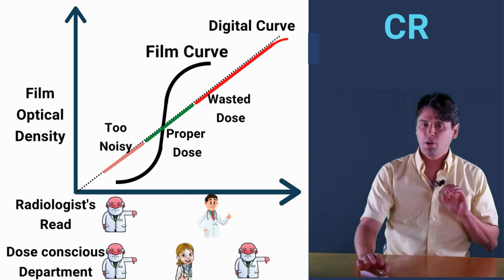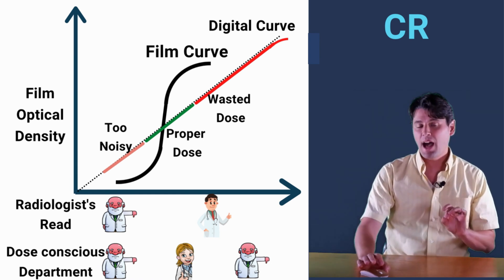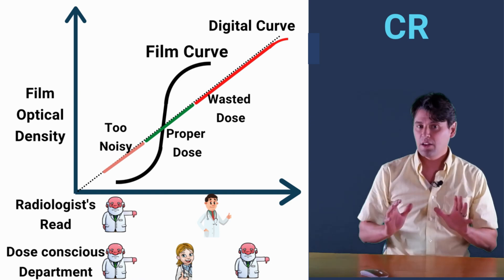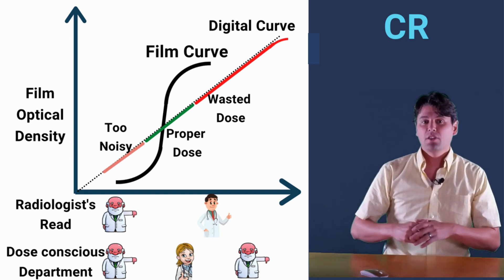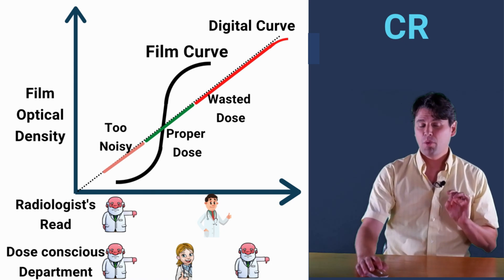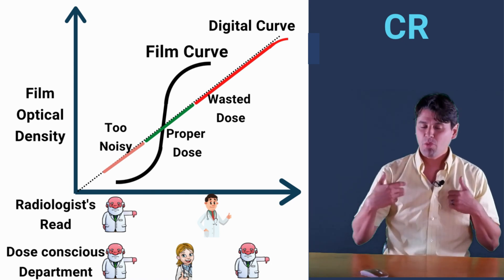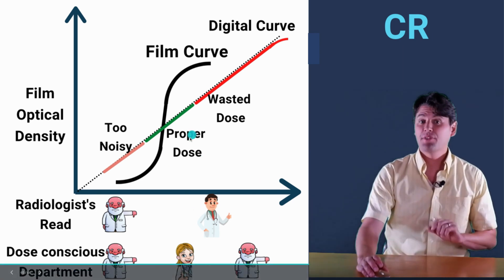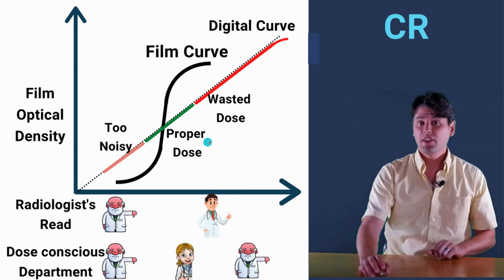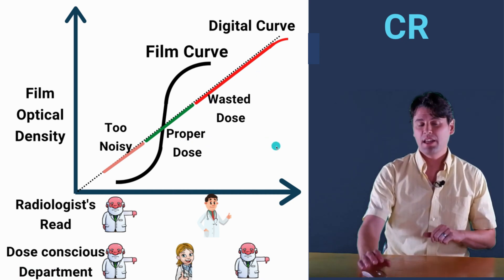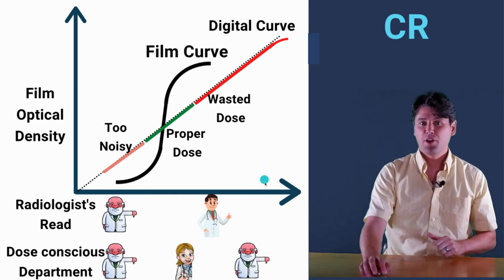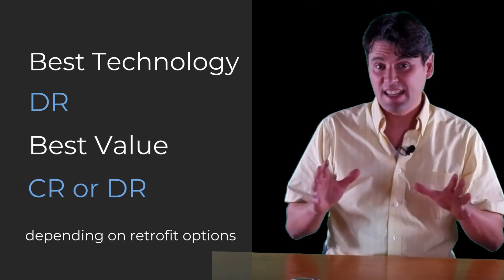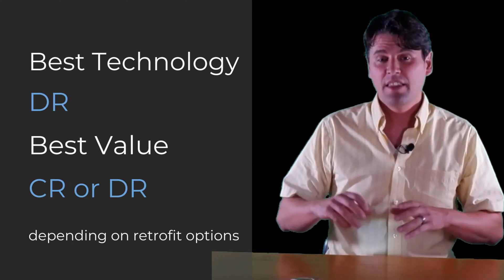In general, the technology behind DR systems is a little more dose-efficient, so DR wins as far as dose efficiency. If done properly, CR can be on the same order as film, but if done improperly CR can actually lead to higher radiation dose than even film. Make sure to dig into the details — we're going to have a playlist that includes detailed CR and DR videos covering how they work from a physics perspective.